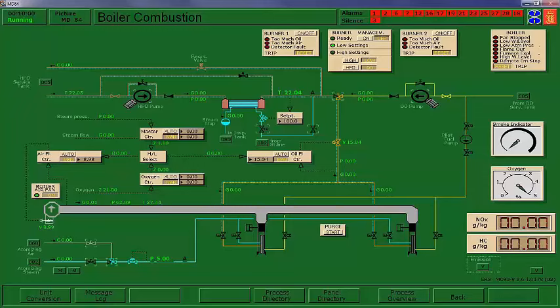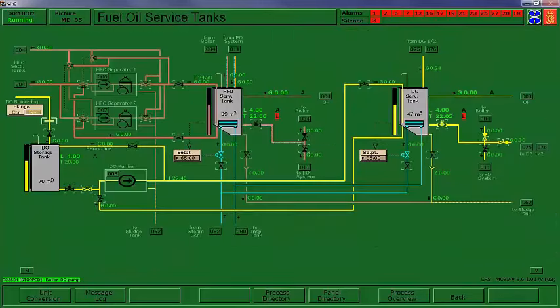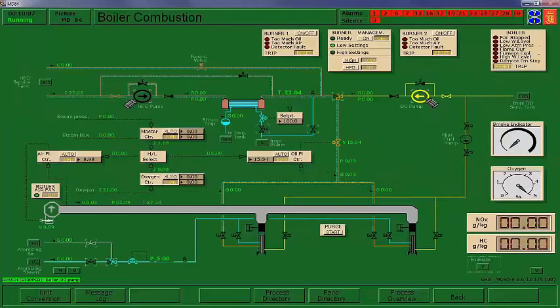But anyway, we'll go ahead and start our diesel oil pump up. I did open up the fuel, so we'll go ahead and start that up. I've got 15% on my fuel oil regulating valve, and about 9% on my forced draft fan damper. That should light. Pilot comes on and ignites the pilot flame. And then you'll see the main valve open and ignite the main fire, and then this will go out again.